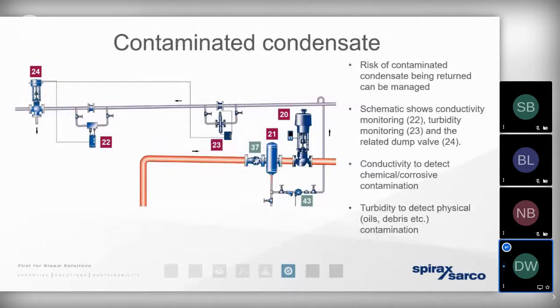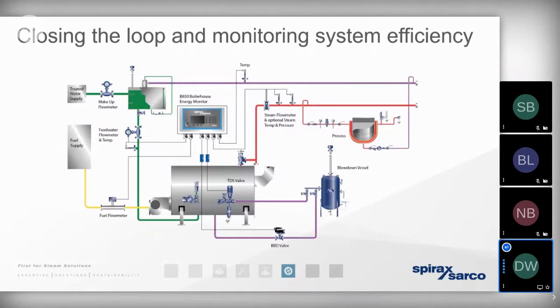But we also know that condensate is often dumped to waste through fear of contamination. The good news is that we can identify that contamination before it is brought back to the boiler house. We can dump it to waste if it is contaminated, but it means that we can help to increase the rate of condensate return as much as is feasibly possible. So I just want to leave you by going back to a solution that we've looked at previously, and that's the boiler house energy monitor.